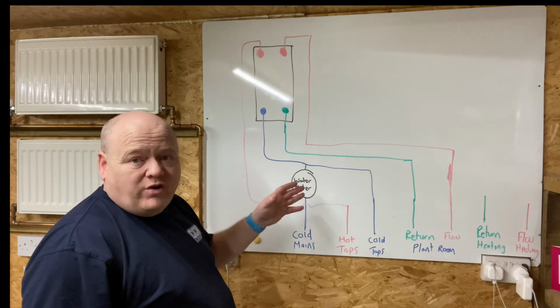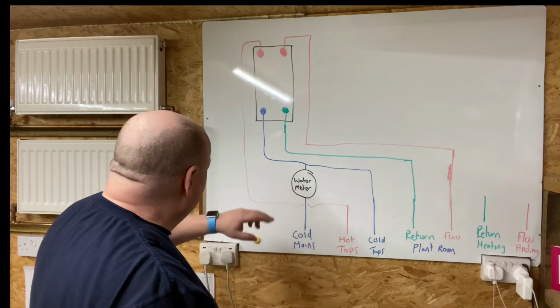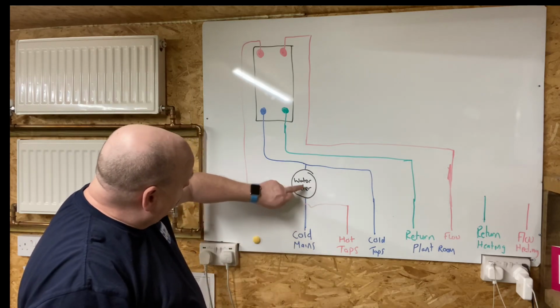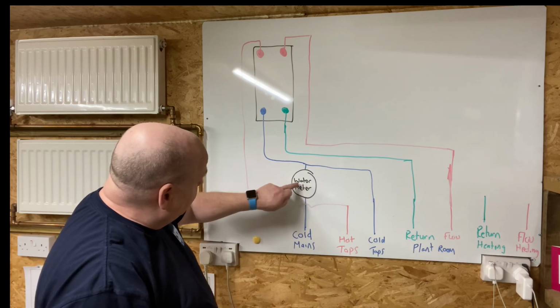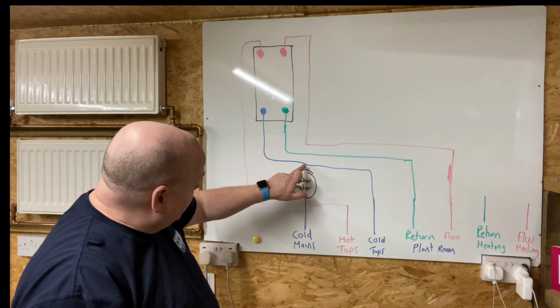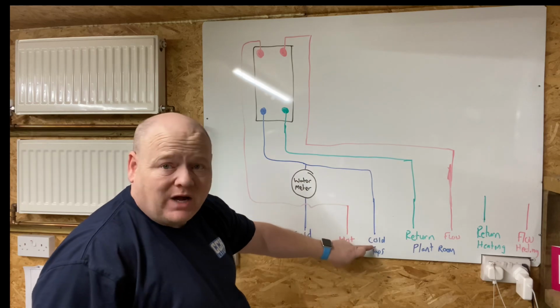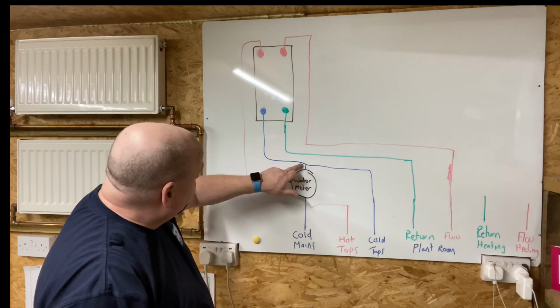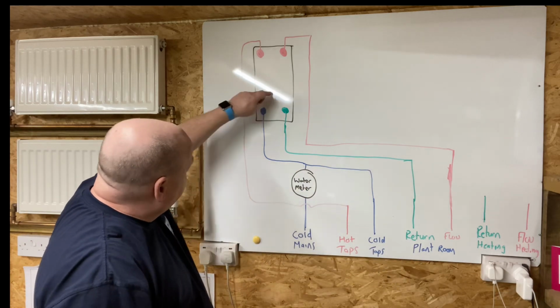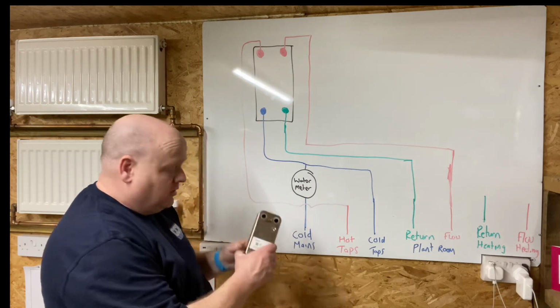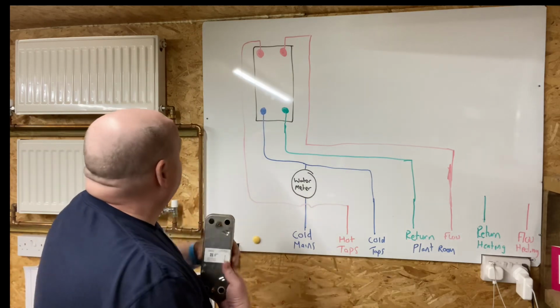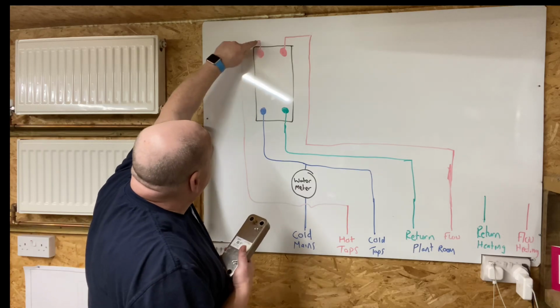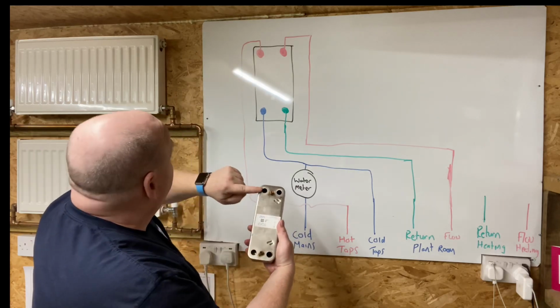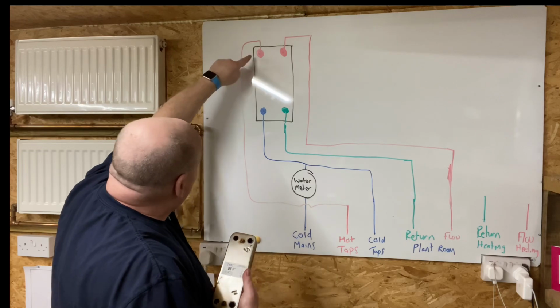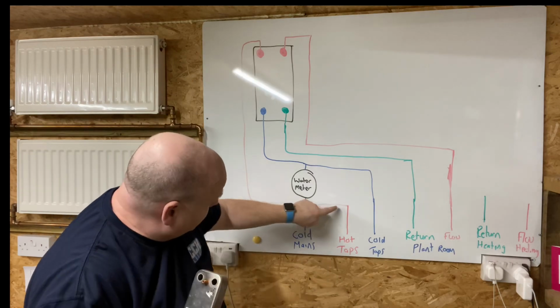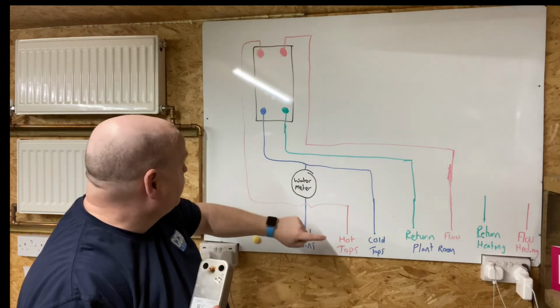So just to try and explain this a little bit easier, again, we've got the cold mains coming in, goes through the water meter, it's got a T on there, one side of it goes to the cold taps in the property, and then one side of it goes to the plate heat exchanger. So that's your plate heat exchanger. And then the other side of it, this goes through here and it comes out here hot, and then that side of it goes to the hot taps.